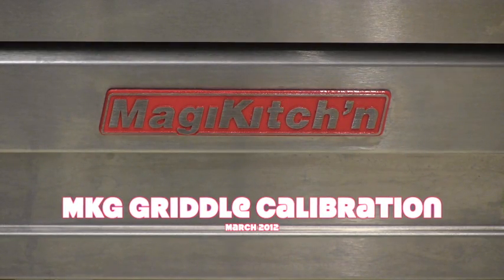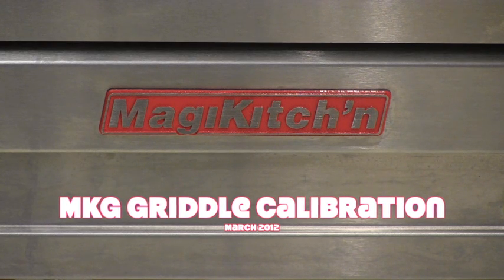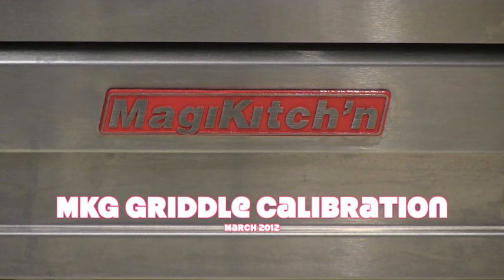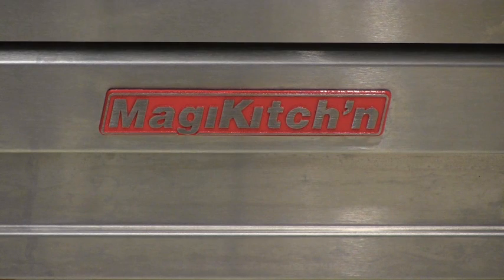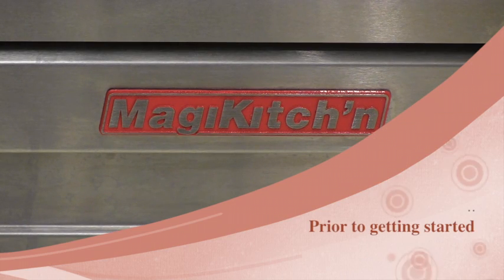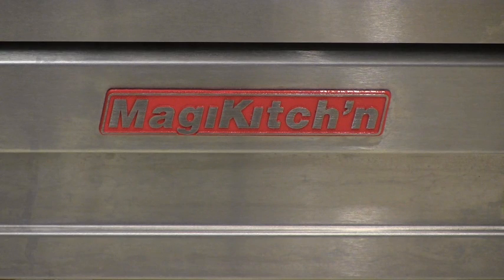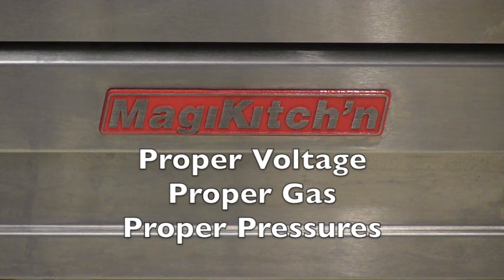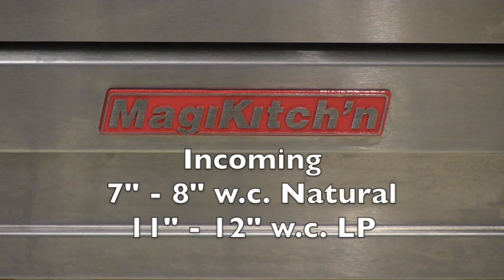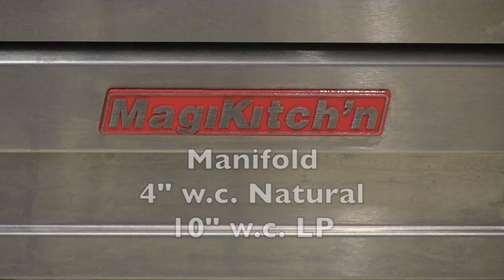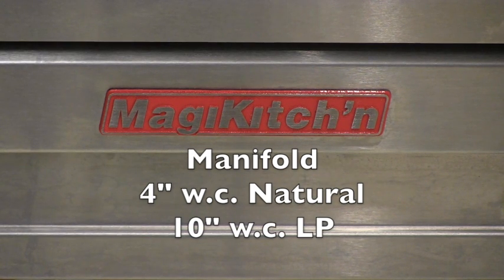In this video, we will review temperature calibration for a solid-state controlled griddle. Before getting started, check to make sure that the griddle is being supplied with the correct voltage, gas type, and pressure. A steady supply of 7 inches to 8 inches water column is required for natural and 11 to 12 inches for LP. Manifold pressure should be 4 inches water column for natural and 10 inches water column for LP.